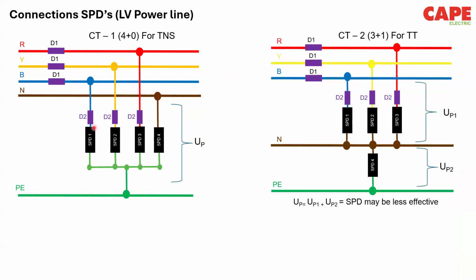there are two UPs. That is, SPD 123 will have one UP value, and the SPD between neutral to PE will have the next UP value, which makes it a little bit less effective. If you take the total voltage protection level for a 3+1 SPD, it will be higher. And if the manufacturer has not declared the value, the standard says you just add these two UP values. And generally it will be double the UP value.